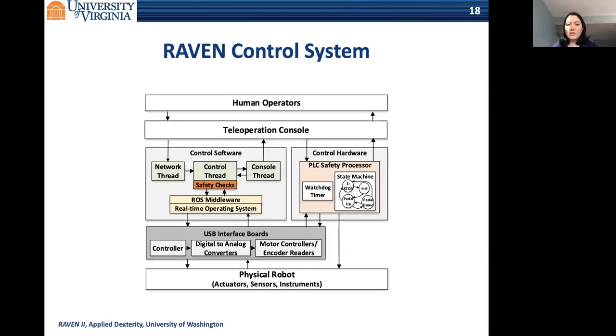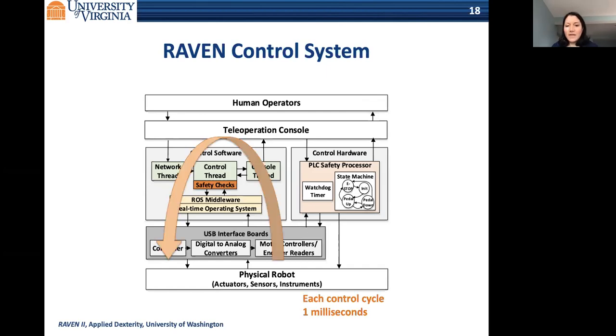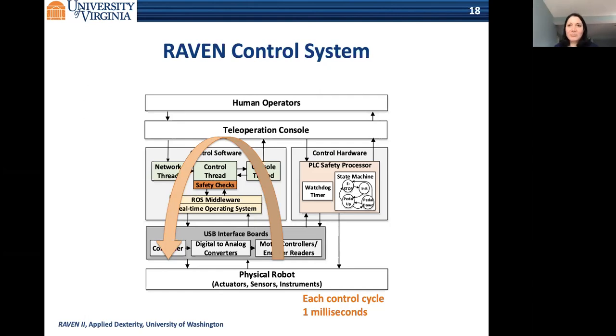Here is how the Raven control system looks. Inside the control software, we have a multi-threaded application running on top of a real-time operating system—an RT-PREEMPT version of Linux—with ROS tasks running on top of it. Everything in the control software must execute within a time constraint of one millisecond, since a human operator issues commands in milliseconds and must see the response. This one-millisecond real-time constraint is very tight for designing the safety monitor—if placed in the control loop path, it must complete all computations within that constraint. We are considering hardware acceleration techniques to speed up monitoring as it becomes more complex.